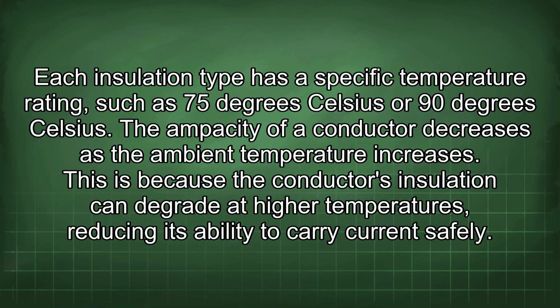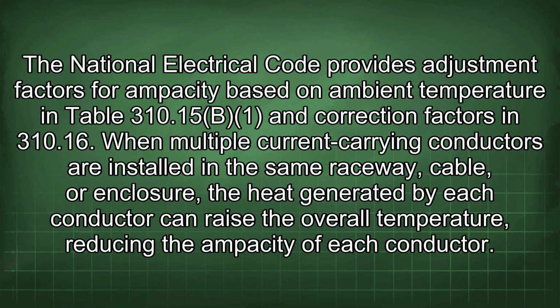The ampacity of a conductor decreases as the ambient temperature increases. This is because the conductor's insulation can degrade at higher temperatures, reducing its ability to carry current safely. The National Electrical Code provides adjustment factors for ampacity based on ambient temperature in Table 310.15(B)(1) and correction factors in 310.16.